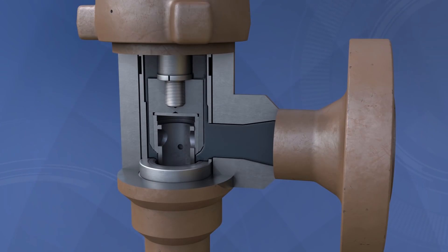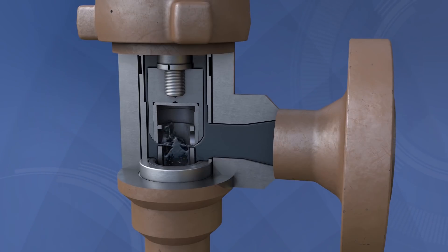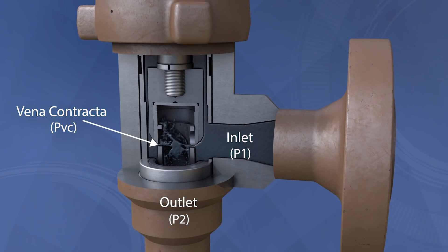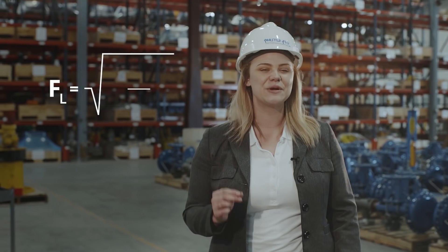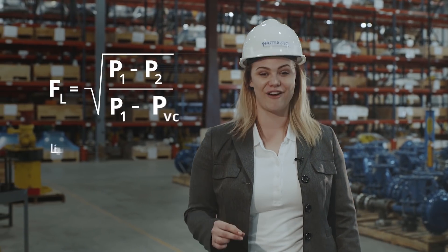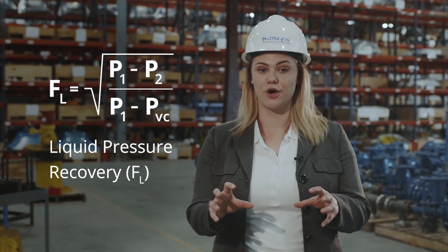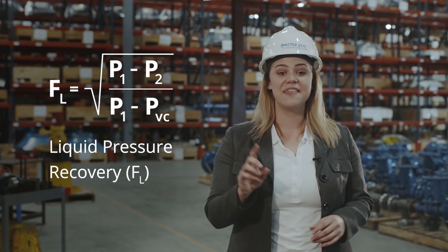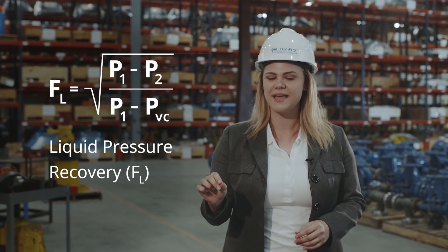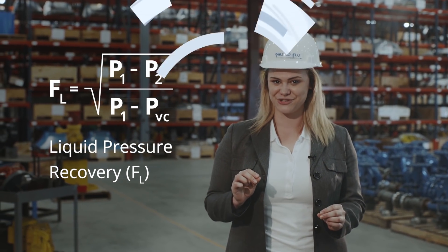In production, only inlet and outlet pressure values are measured. However, inside the valve at the throttling point, the pressure is much lower. This is designated as the Vena contracta pressure. That brings us to another important factor of the choke valve selection process: liquid pressure recovery. This is the ratio between the pressure drop and the difference between the upstream and the Vena contracta pressures.